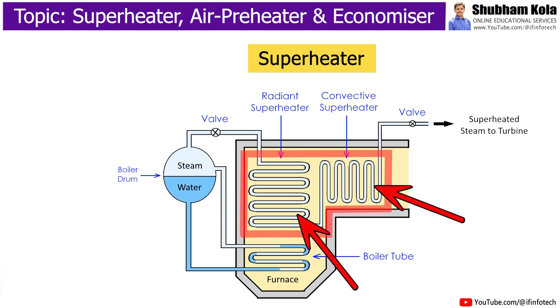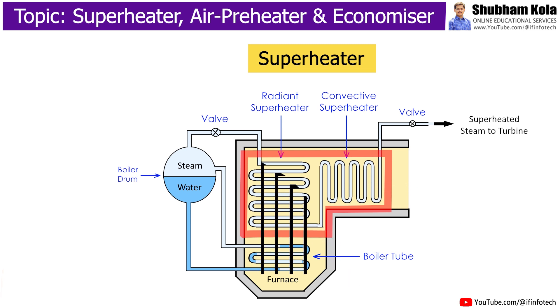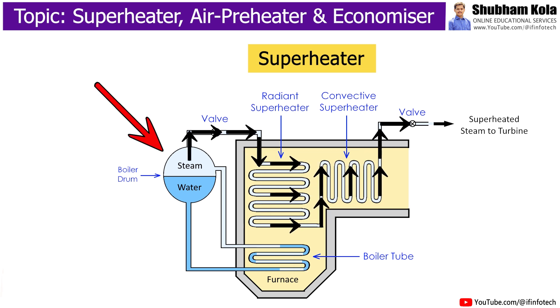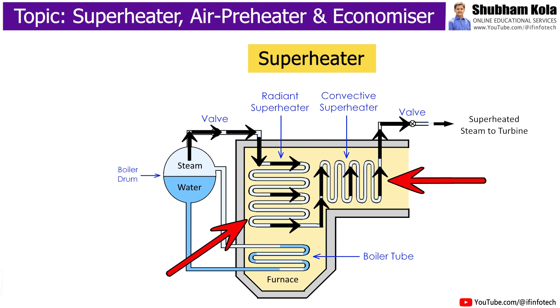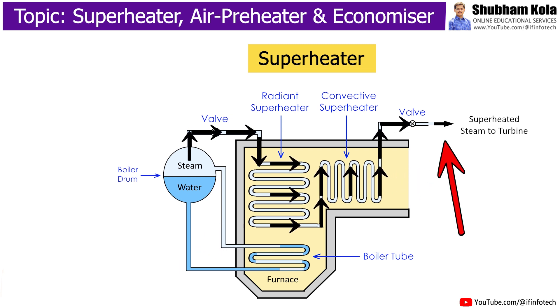The superheater tubes are heated by the heat of flue gases during their passage from the furnace to the chimney. The saturated steam from the evaporator drum is passed through the superheater tubes and is converted into superheated steam. This superheated steam is supplied to the turbine to rotate the turbine blades for generation of electricity. Thus, the function of the superheater is to convert saturated steam into superheated steam.